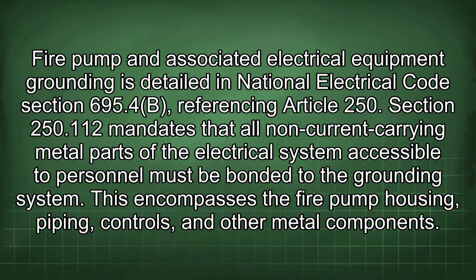Fire pump and associated electrical equipment grounding is detailed in National Electrical Code Section 695.4(B), referencing Article 250. Section 250.112 mandates that all non-current carrying metal parts of the electrical system accessible to personnel must be bonded to the grounding system. This encompasses the fire pump housing, piping, controls, and other metal components.